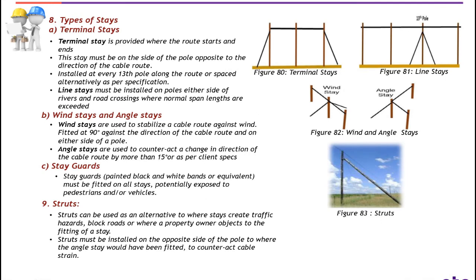Types of stays. In this slide we will talk about different types of stays. Number one: terminal stays — terminal stays are provided where the route starts and ends. This stay must be on the side of the pole opposite to the direction of the cable route. Installed at every 13th pole along the route or spaced alternatively as per specifications. Line stays must be installed on poles either side of rivers or road crossings where normal span lengths are exceeded.